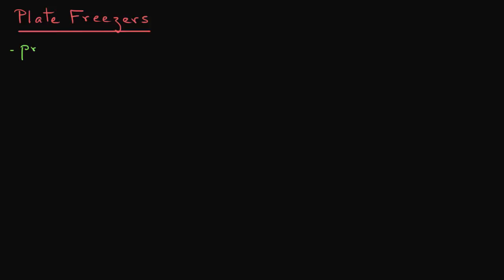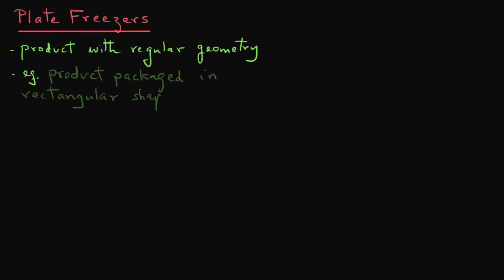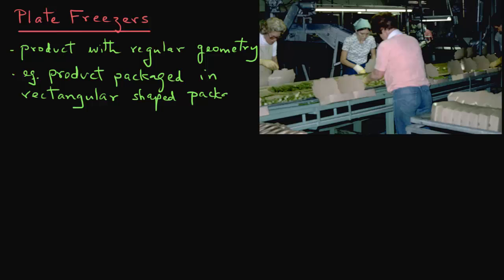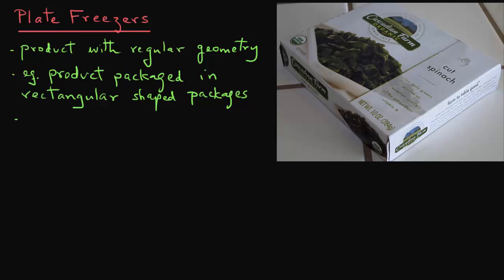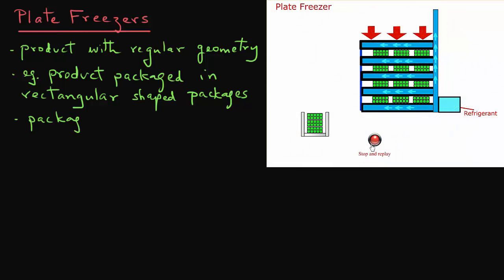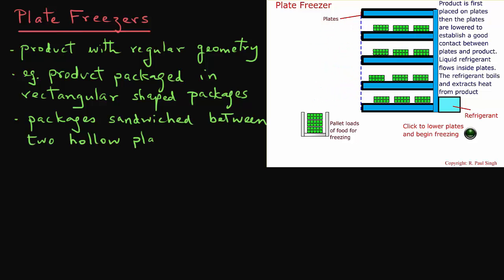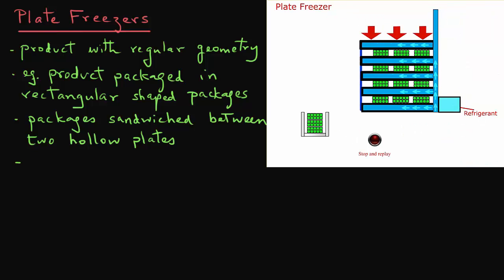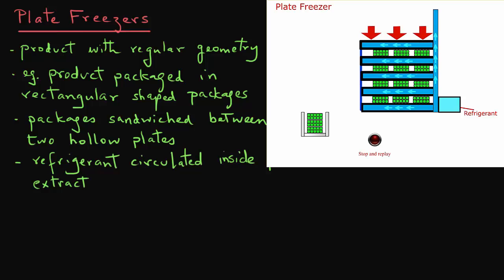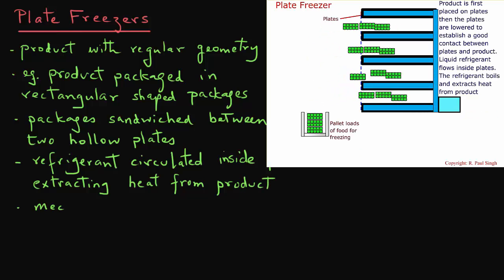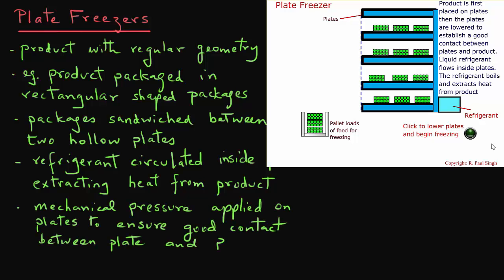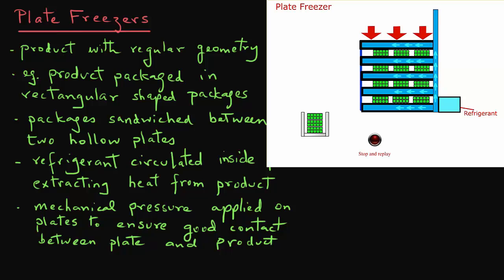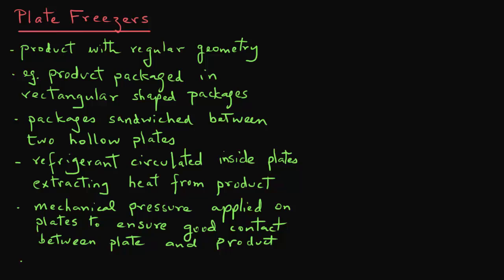In plate freezers, we use a product with regular geometry, meaning the product is packaged in rectangular shaped packages. This is a requirement of this type of freezer because the packages are sandwiched between two hollow plates of the freezer. Once the plates make contact with the package, refrigerant is circulated inside those plates to extract heat from the product. Also, mechanical pressure is applied on the plates so that there is good contact between the plate and the product, as we see in this animation.